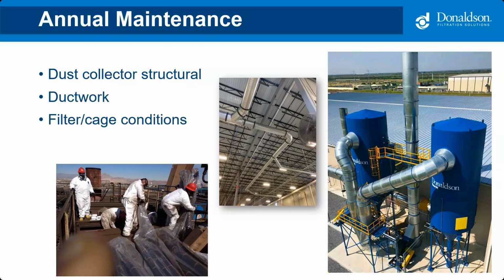For baghouses, I also recommend that you check the cages that go inside the bags. Over time, those cages can corrode or lose their structural integrity, and then your bag will essentially collapse on itself, and now you've just lost all the filtration capability out of that bag. And typically, if you've got one cage that's starting to corrode and fail, there are more in your collector that are dealing with that as well. So it's good just to check those cages, see if any need replaced. And if you are doing a filter replacement, you're going to want to check all those cages, because when you order the filters, you're going to want to order new cages as well to go with those filters.